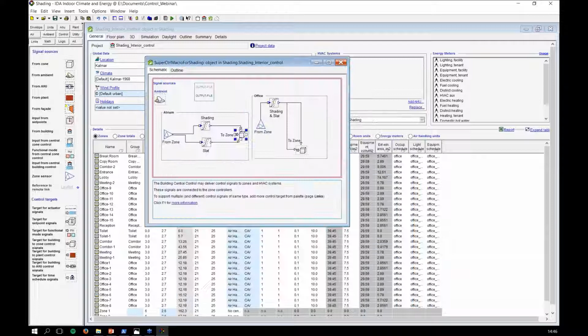So that zone signal is coming to a proportional controller, one for the shading and one for the slat angle. This one will give me an output between 0 and 90 degrees, and this one should give me an output between 0 and 1, 0 being undrawn and 1 being drawn. I'm sending this signal to the zone, and I'm calling this target my zone target atrium, building to zone control atrium. If I open this, I'll see that my controllers are connected, one to shading and the other one to slat angle.